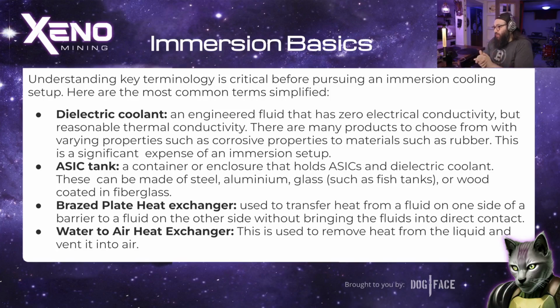There's also a water to air heat exchanger, which removes heat from the liquid and vents it into air. So there are two ways to do this: double loop and single loop immersion setups, but both can use water to air heat exchangers as well as brazed plate heat exchangers for a double loop setup.